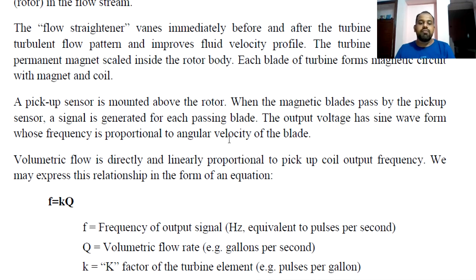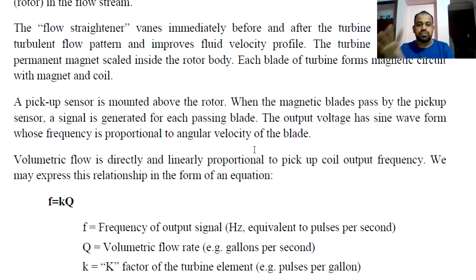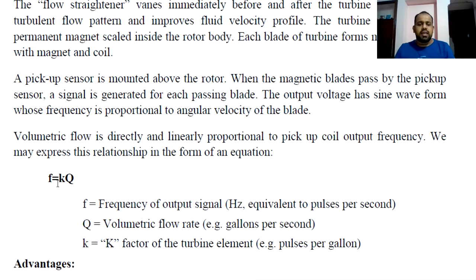The output voltage is a sine wave whose frequency is proportional to the angular velocity of the blade. Volumetric flow is directly and linearly proportional to pickup coil output frequency. We may express this relationship as: Fn = k × Q, where Fn is the frequency output of the magnetic pick-up coil, k is the meter factor of the turbine element, and Q is the volumetric flow rate.